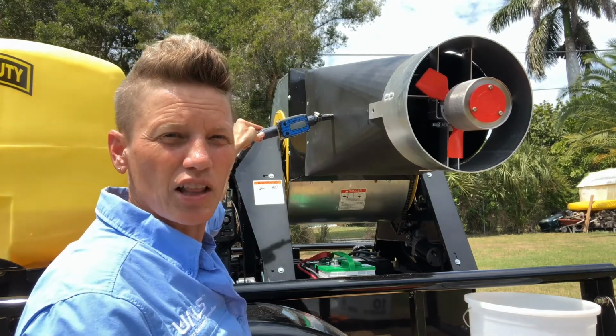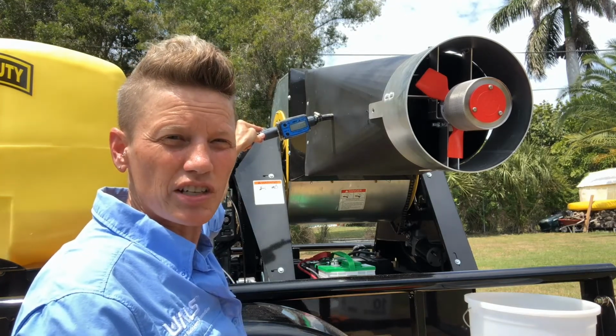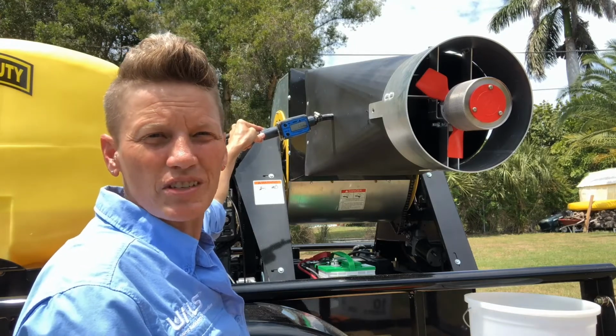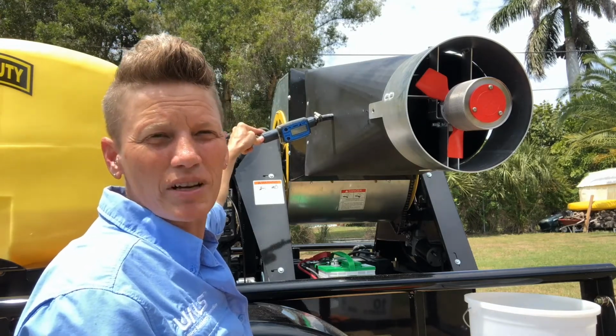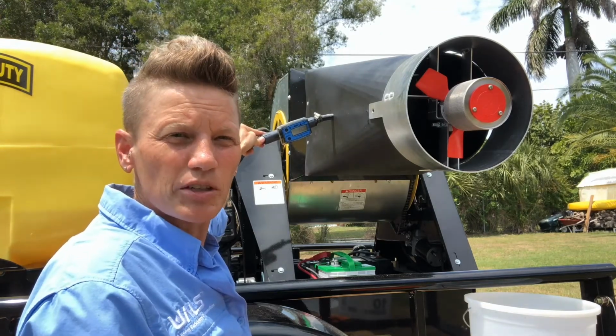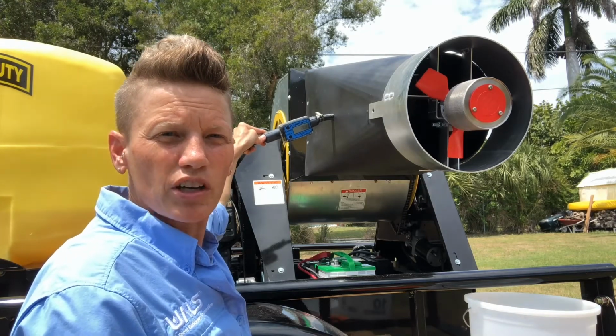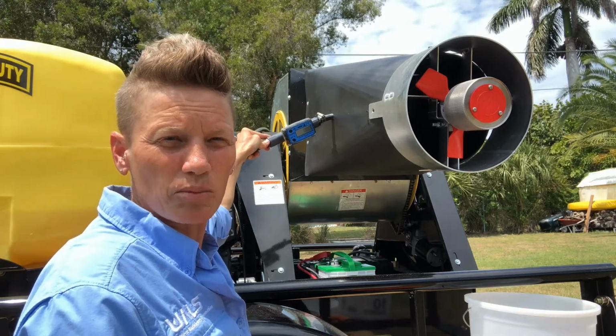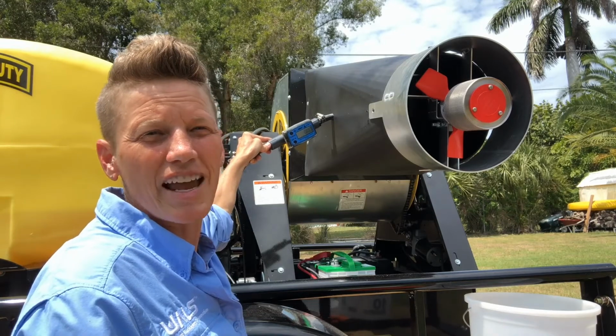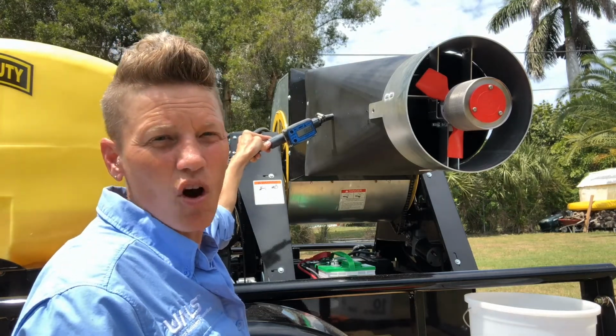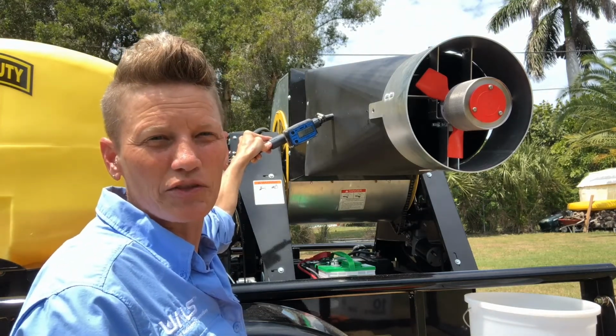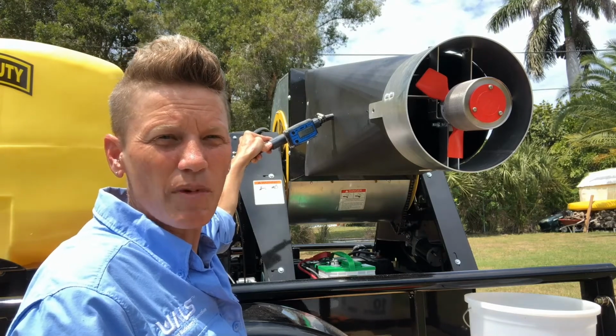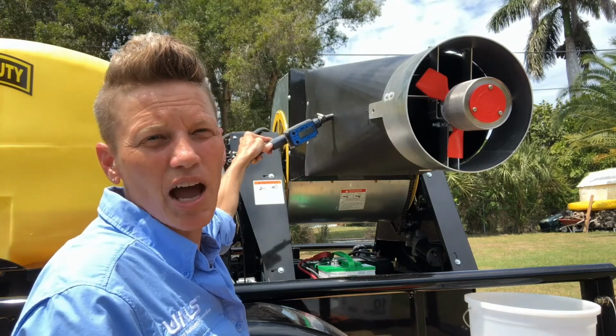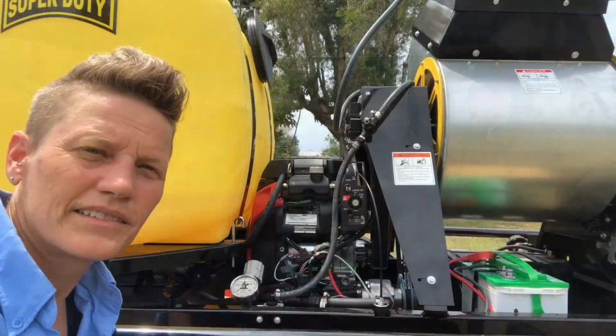It has another calibration mode called field calibration, which is used for more viscous material. So for example, if you're mixing a 24% VectoBac WDG solution, you may want to go through the steps of field calibration to make sure that your flow meter is accurate. As a general statement, it is always valuable to calibrate your flow meter to make sure that it is measuring accurately. We've already done that prior to this calibration.